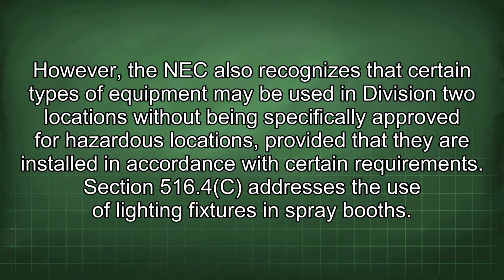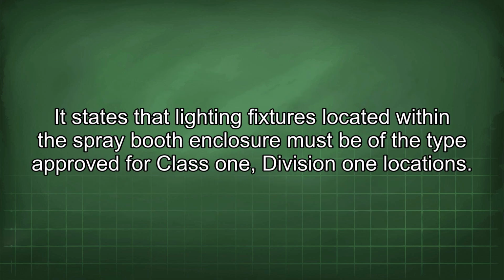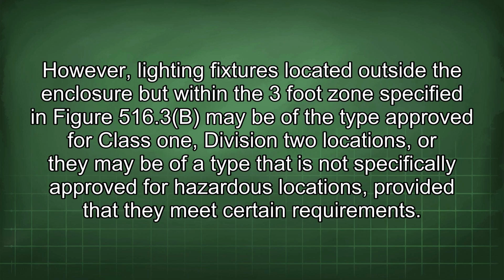516.4c addresses the use of lighting fixtures in spray booths. It states that lighting fixtures located within the spray booth enclosure must be of the type approved for Class 1, Division 1 locations. However, lighting fixtures located outside the enclosure but within the 3-foot zone specified in Figure 516.3b may be of the type approved for Class 1, Division 2 locations, or they may be of a type that is not specifically approved for hazardous locations, provided that they meet certain requirements.